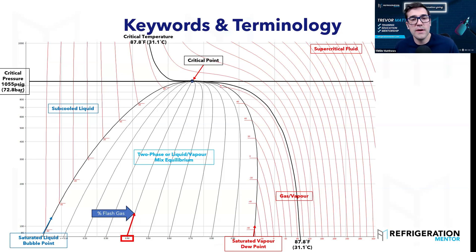There are theoretical calculators for that inside the manufacturer's controller. When we're running that high, what is it doing? It's calculating, in these high-pressure controllers, the best coefficient of performance. It's trying to maintain - I shouldn't even say the least amount of flash gas - the best amount of flash gas going into that receiver to maintain the amount of work for those transcritical compressors or the parallel compressor, depending on the system. That's really what it's doing inside that high-pressure valve controller. It's going to move the pressure up or move it down to kind of maintain the best net refrigeration effect that you can get for that system on those particular conditions.